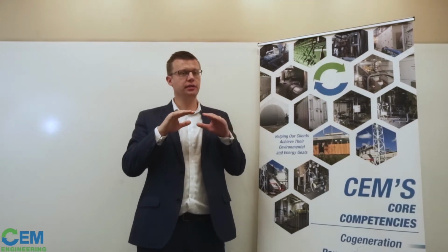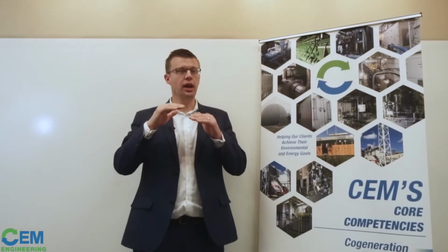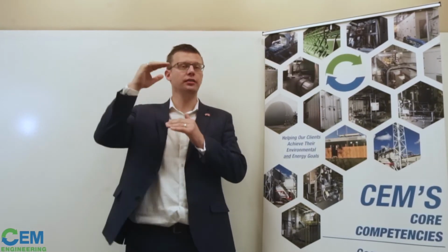In today's economy, in today's energy marketplace, the price of electricity continues to go up, and that burden is being borne by universities or industrial customers who have to consume that electricity. And so the price for electricity continues to go up to 12, 13, 14, 15 cents per kilowatt hour. At the same time, the price of natural gas, because there's so much of it available, is very low. And as those become farther apart, we call the distance between those the spark spread, because when you have a combustion turbine or a reciprocating engine, there's a spark in there that drives the engine. So we call that the spark spread.